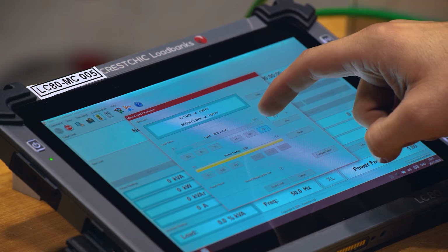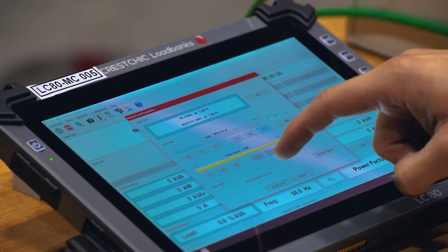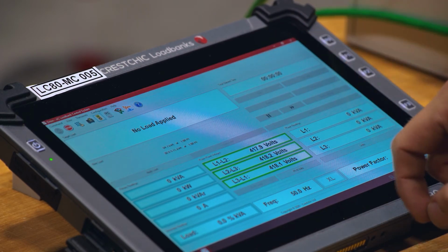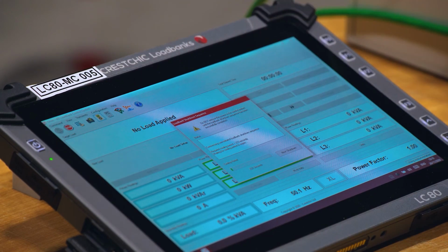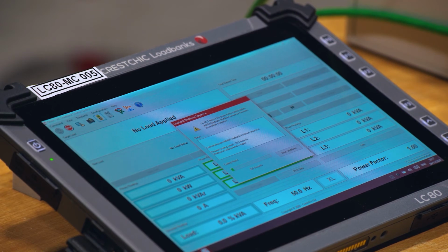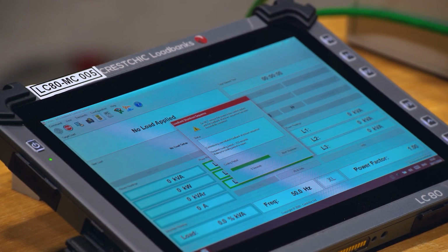After various loads have been applied, the load can be removed and the shutdown sequence can be started. This is started by pressing the stop button in the Orion software. Once pressed, the load bank requires 4 minutes for the fans to run on and cool the elements to a safe temperature. Once the countdown timer has finished, the cooling fans will stop and the shutdown sequence is now complete.